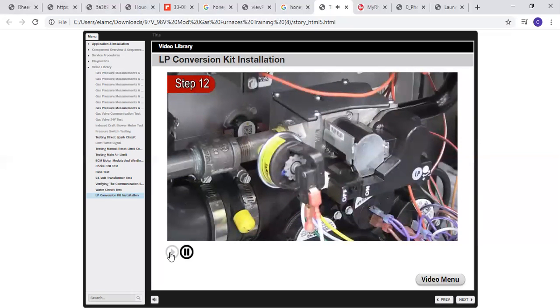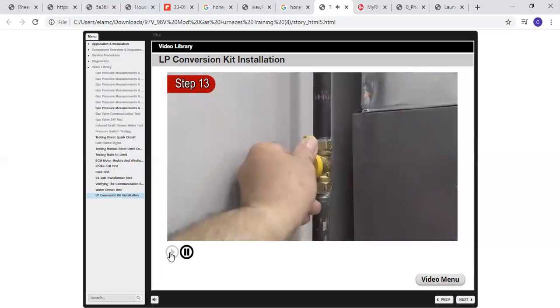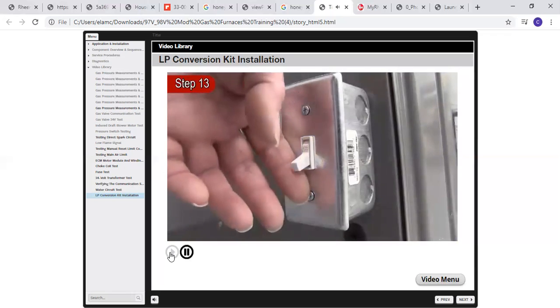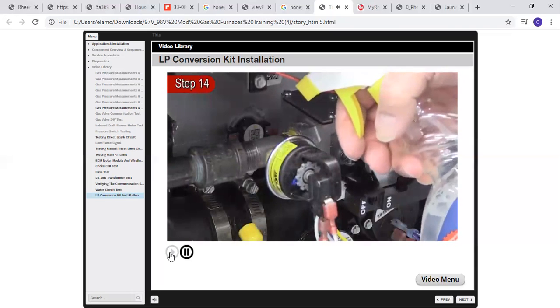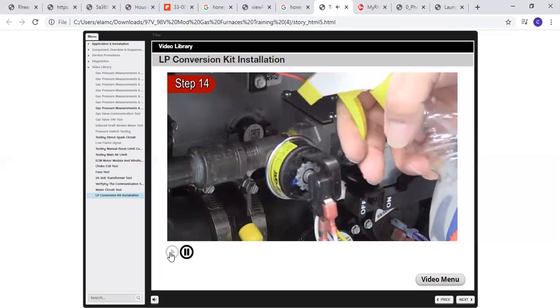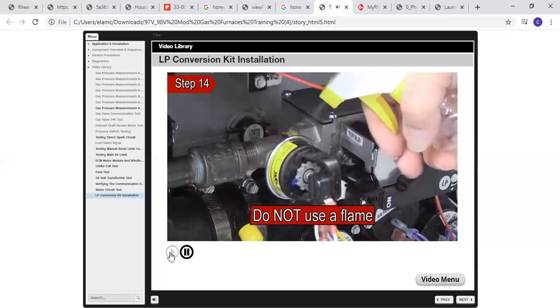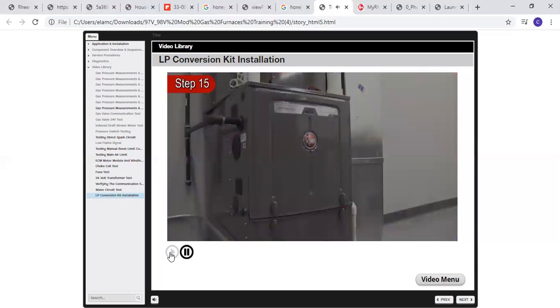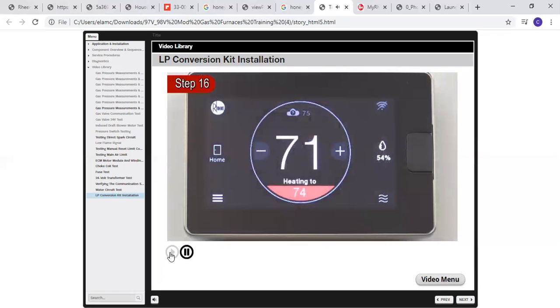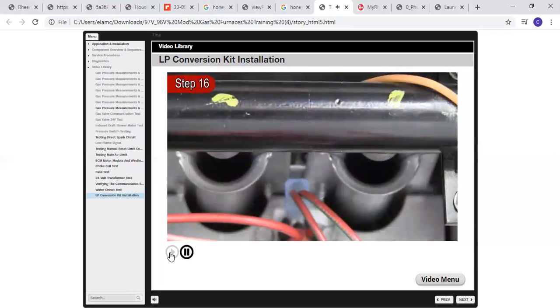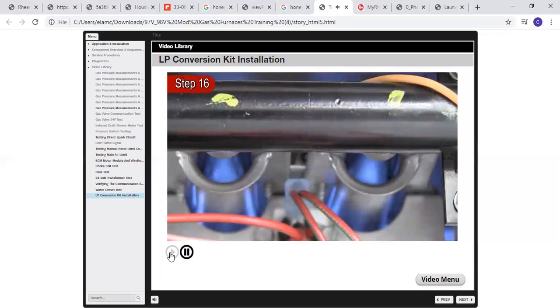Step 12. Reconnect the gas supply line to the furnace. Step 13. Turn on the gas supply and electrical supply. Step 14. Check unit thoroughly for gas leaks with soap and water, not with a flame. Step 15. Follow lighting instructions to put the furnace into operation. Step 16. Operate the thermostat to check unit operation for ignition and extinction characteristics.